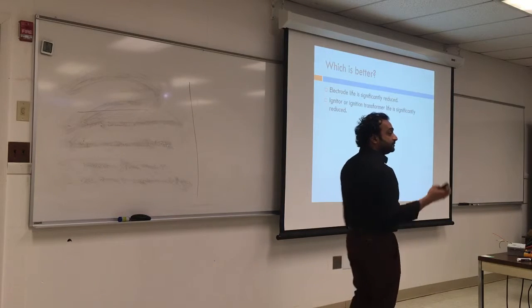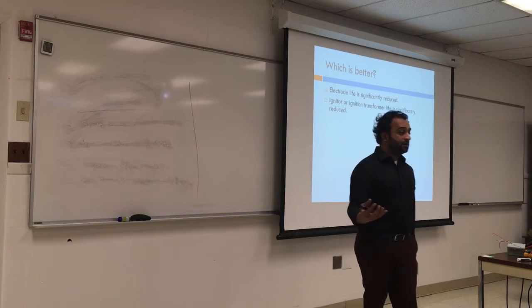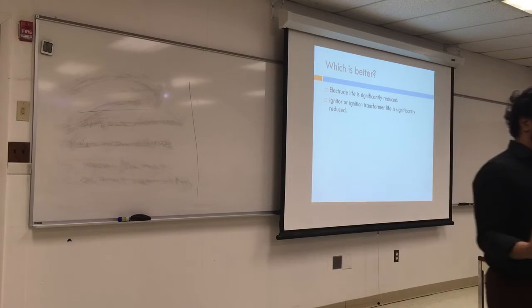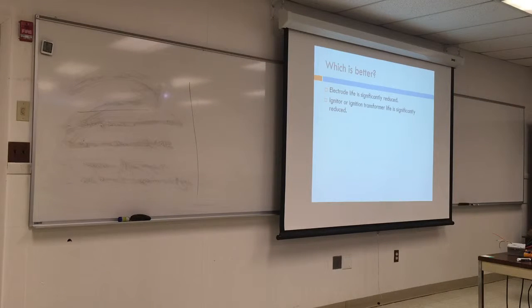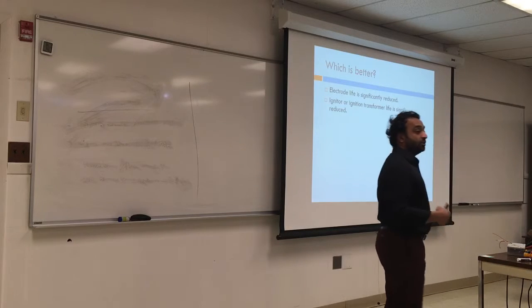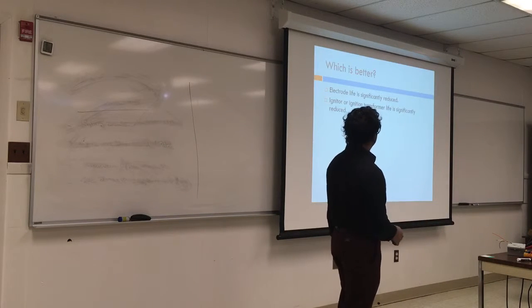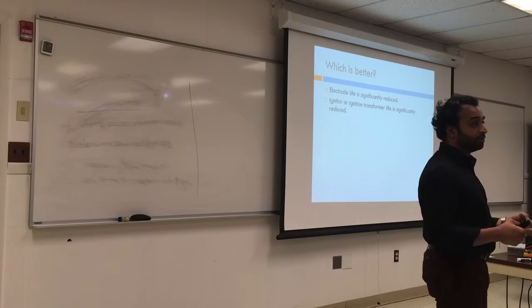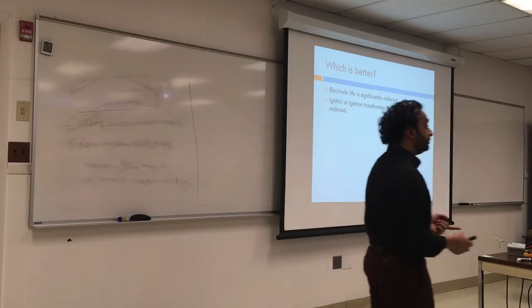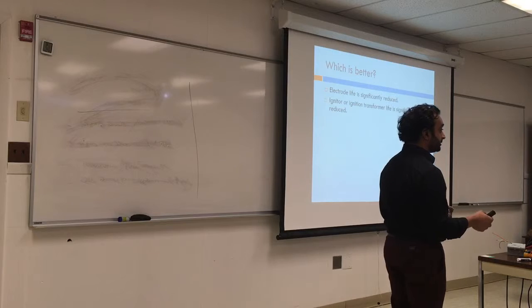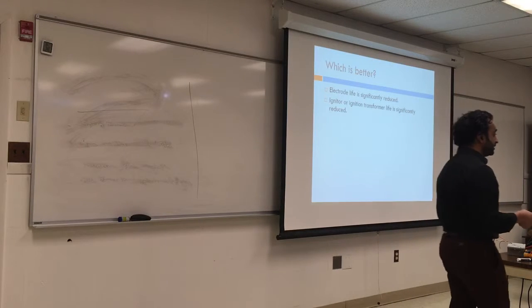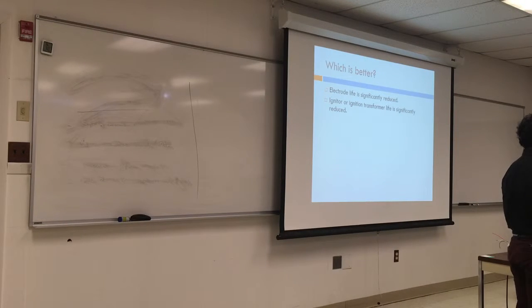So which is better, to have continuous spark or intermittent spark? If we have the ignition on the entire time, it will definitely use up the electrode's life. Again, with continuous spark, it will wear out, probably within 6 months, and they will get shorter. You understand? It will consume too much energy, and it will also wear out the electrodes. The tips will get shorter and shorter.